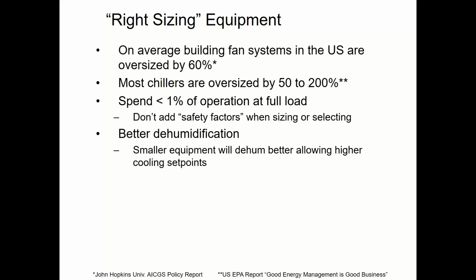If your system's oversized, your thermostat asks for cooling. It provides a lot of cooling because it's oversized. It satisfies the thermostat very quickly, which sounds like a good thing, but it's actually horrible because it didn't run very long, which means I never got down to the point of dehumidifying the air. I need the system to run for a long time. I need every time the cooling kicks on for it to run 15, 20, 25 minutes at a crack, preferably longer. I finally have my system in my house kind of optimized, and it'll run in the summertime 4, 5, 6 hours at a crack without even cycling off once.